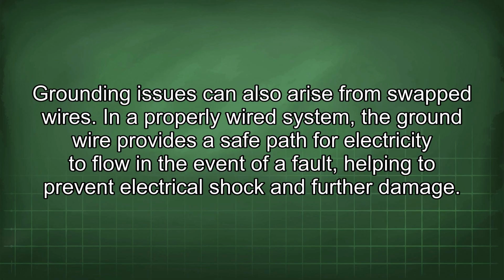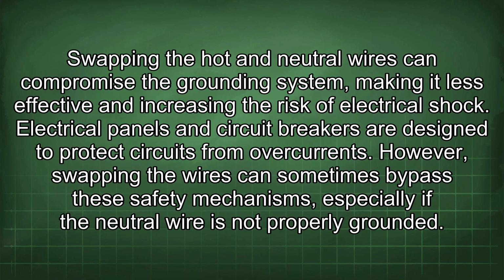Grounding issues can also arise from swapped wires. In a properly wired system, the ground wire provides a safe path for electricity to flow in the event of a fault, helping to prevent electrical shock and further damage. Swapping the hot and neutral wires can compromise the grounding system, making it less effective and increasing the risk of electrical shock. Electrical panels and circuit breakers are designed to protect circuits from overcurrents.